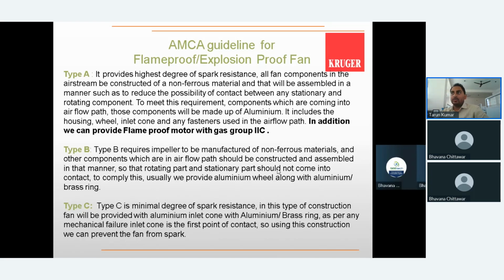Then type B says that out of the rotary and stationary parts, one part should be non-ferrous. Either it can be the impeller or the inlet cone. AMCA type C says that between the rotary and stationary part there is a non-ferrous material, like a brass ring between the impeller and inlet cone. By that construction you can make your fan completely flame proof. These are the three major guidelines we have to follow for any chemical exhaust, or any application where a spark can be generated. Our purpose is basically to avoid sparks.